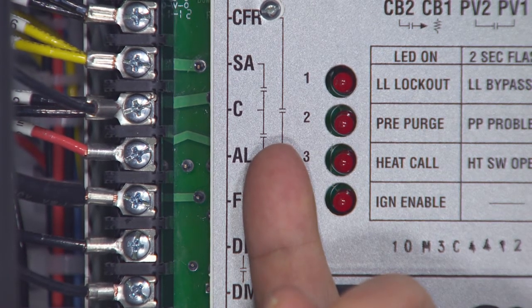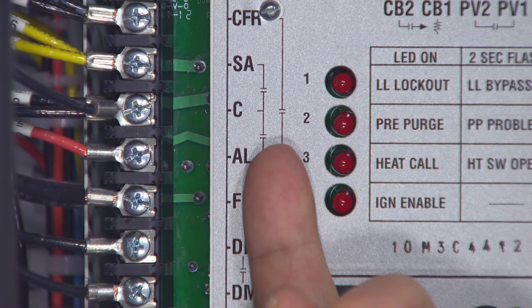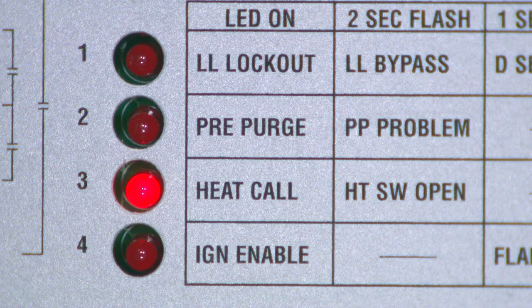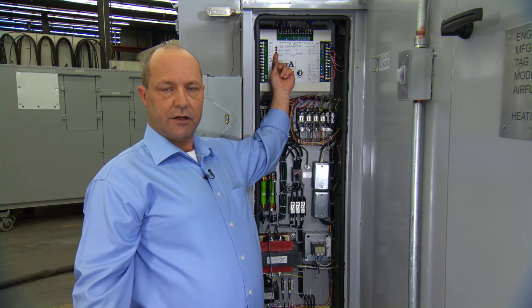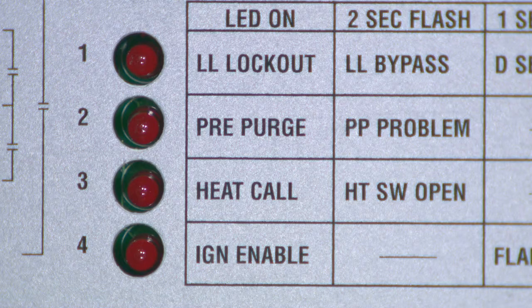After the low-limit bypass cycle is complete, light 1 will go off. If there is a call for heat from the discharge air sensor, the number 3 light will be on for heat call. Light number 2 will come on steady, indicating pre-purge mode, and combustion air blower will run at full speed. After 45 seconds, light 2 will go off, and combustion air blower will go to light off speed. Light number 4 will come on steady, indicating ignition enable. Burner is on.